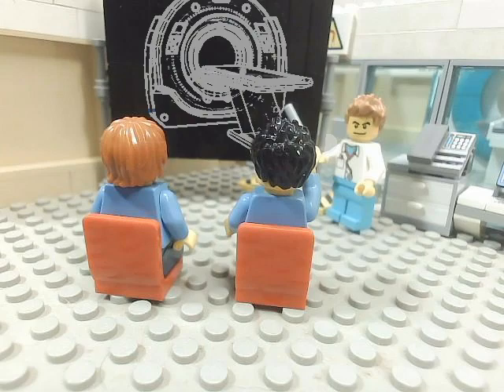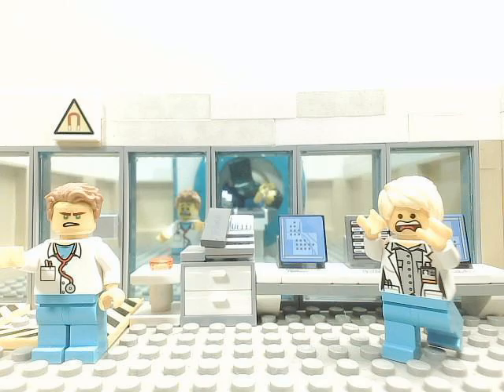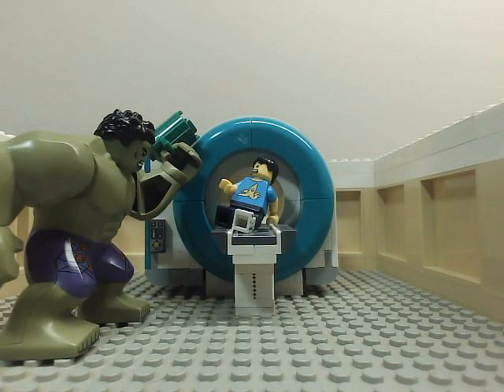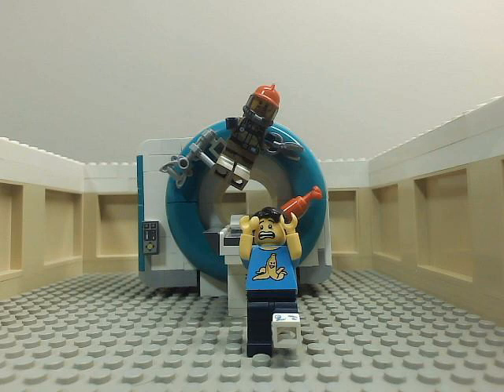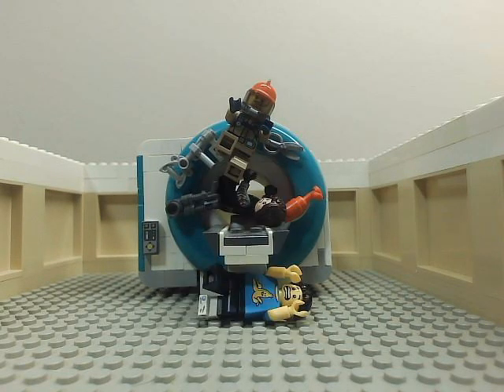The magnet is very strong. It can pull an office chair into it with over a half ton of force. The force changes rapidly in space — a slight tug on something can become a Hulk-smash a half a step closer to the magnet. All ferrous things — keys, scissors, air tanks, fire extinguishers, firearms, bionic arms — need to stay out of the magnet room or they can become a projectile which will injure or pin someone to the magnet.